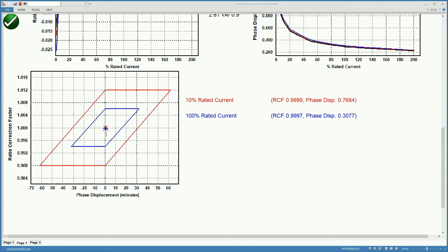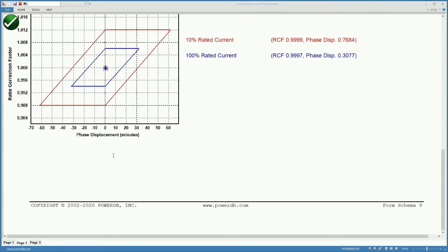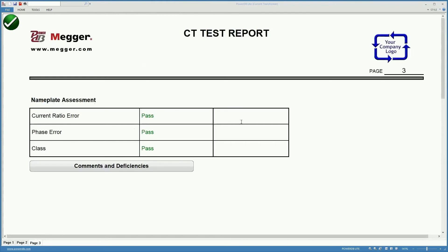Any location of the point here for a particular CT inside the 100% rated current parallelogram would mean that the CT is in good condition. Inside the 10% rated current that means that you have to deal with a little bit of a higher error in that case.